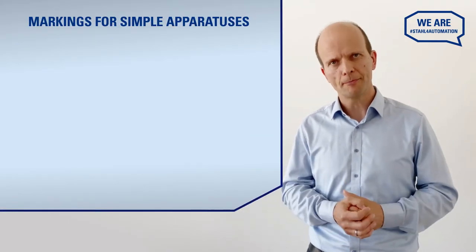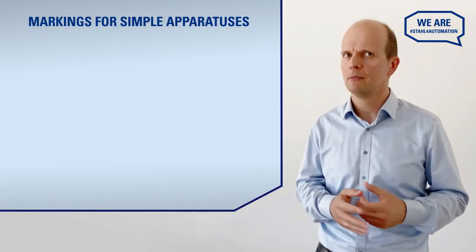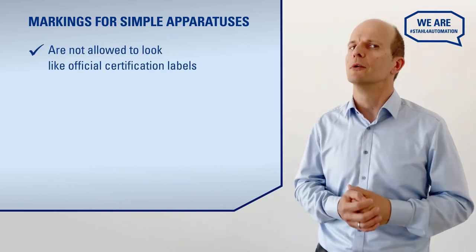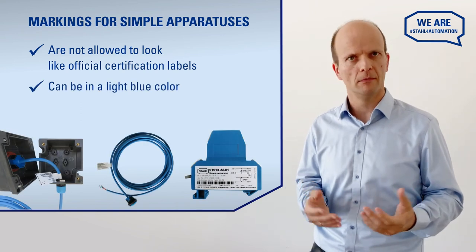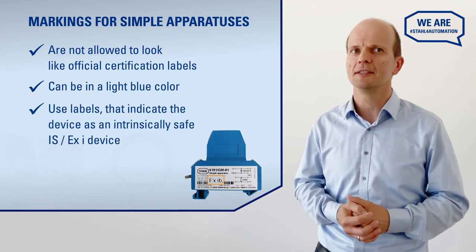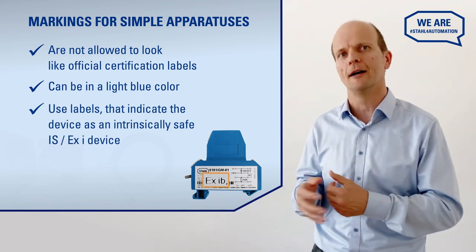Why? Intrinsically safe loops are required to be specially marked, and the simple apparatus is part of such a loop. Just imagine when somebody needs to check these circuits a few years down the road — they should immediately recognize that it contains an IS circuit. As a rule, these markings must be very clear, but they are not allowed to look like an official certification label. The simplest way would be to use light blue color or labels that indicate the device as an intrinsically safe IS or Ex i device.